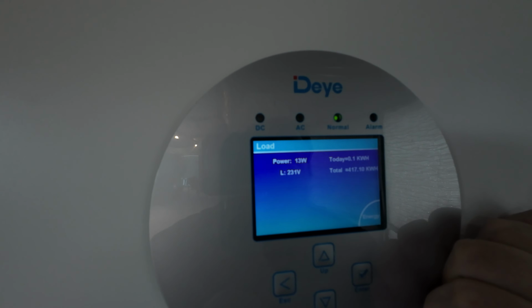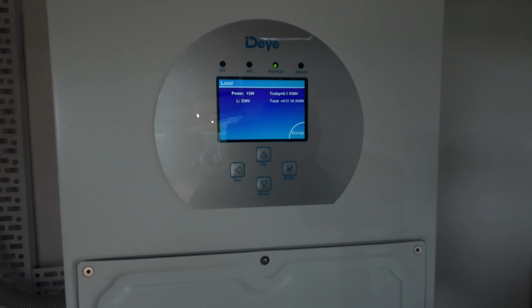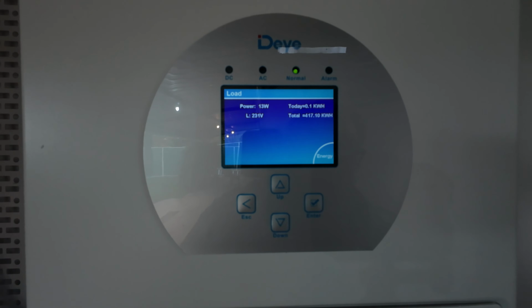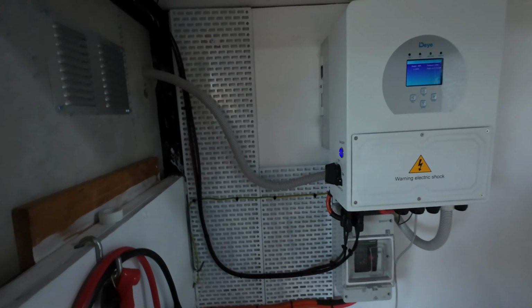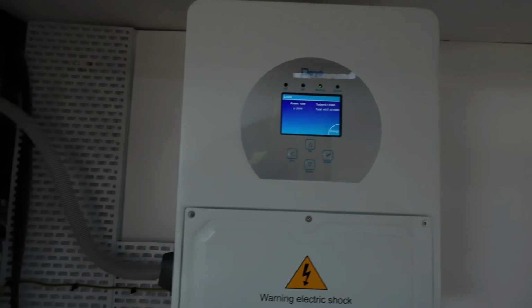The 8 kilowatt, which we're using, is on there, that's the red, and the 5 kilowatt is the green. You'll notice the standby power of the 5 kilowatt is 13 watts. That's what it's consuming. In standby mode, which is what it's always in now, and that is true standby mode. Apart from that tiny little green LED light, it's with nothing else on it until it changes over, and then it takes the whole house on.